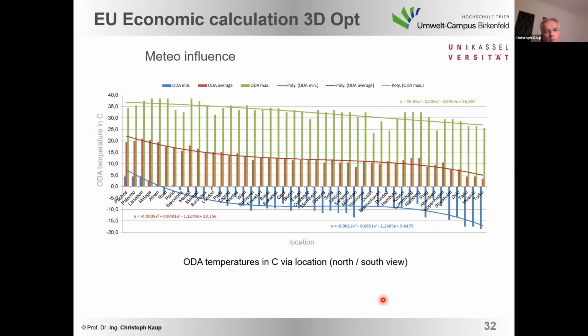And then we did some explorations about how to link the climate zone to the selecting data. And the easiest way, from our opinion, was to link the locations to the outdoor air temperature, because the outdoor air temperature, especially during the winter time, is a selecting value which is given by the customer. And you see, we took here the data from Meteonorm, that in the southern part we had temperatures roughly of 5 degrees plus, and in the northern parts, if you go to Helsinki, we have here a temperature of -18 degrees. So this is the blue line, and here in green we have the summer temperatures. There's also a shift from north to south, and the red line is the average between the both. But at the end, we took the winter temperature because the winter mode determines the heat recovery even in the southern parts.